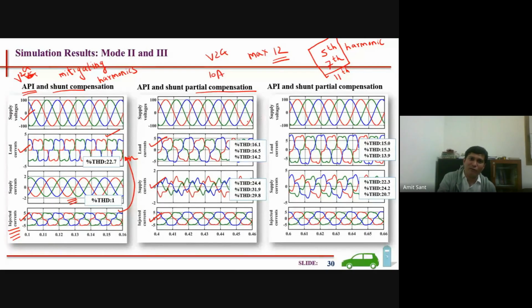But still I'm doing somewhat better than what the THD for this check, it is 16%. Right? The grid THD increased. So this is a disadvantage we are having. Why did this problem occur? Because we did not reduce the harmonics from the grid. So the grid is now supplying 11th, 13th, and so on.